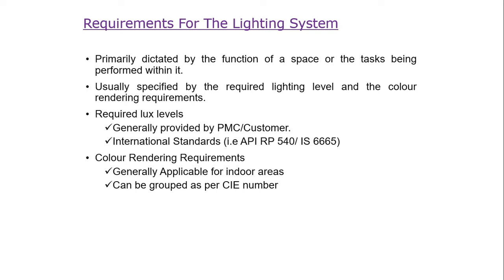The second most important point is the lighting level and the colour rendering requirements. API RP 540, which was discussed in the last slide, specifies the lux level requirement for petroleum processing units. All petrochemical, oil and gas projects refer to that particular standard API RP 540, in absence of a client-specific requirement, to check what is the lux level required for a warehouse, a process plant, a control room, or an OHC room. All those are broadly defined in that standard.